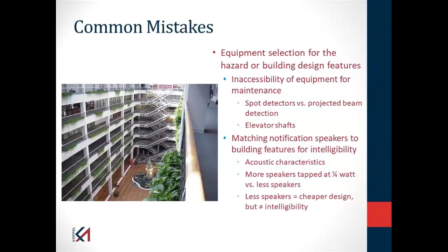And another related to equipment is not selecting the proper equipment for the environment. So this is actually a janitor's closet in a hospital. You can see at the top a concealed sprinkler just to the right of the light fixture. I can see a smoke detector, and I can see a hot water dispenser. And what happens in this scenario is housekeeping will often go in. Notice there's a self-closing device on the door. The door closes behind them. They put a bucket underneath this hot water dispenser. Look how close it is to the smoke detector. The next thing we know, we fill this room with steam, we get a smoke detector on.